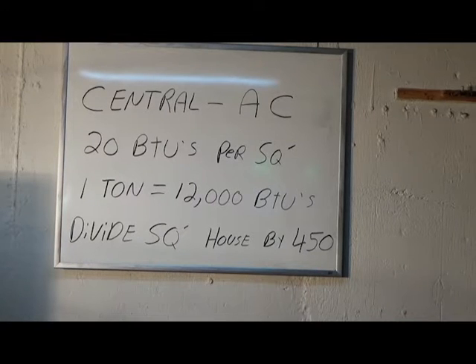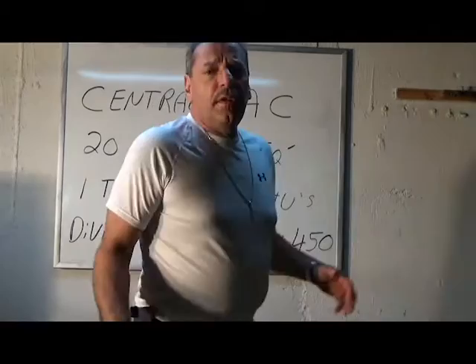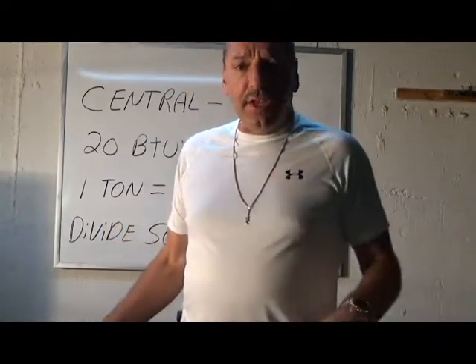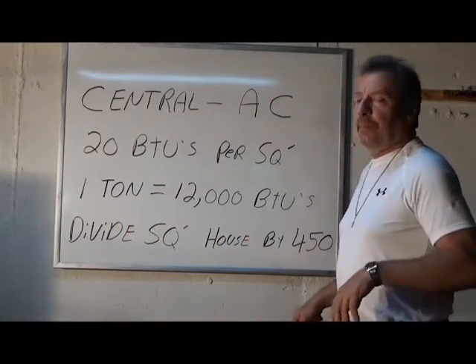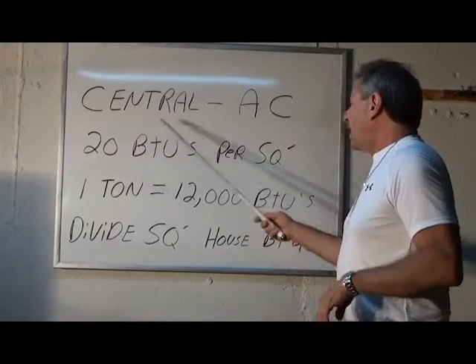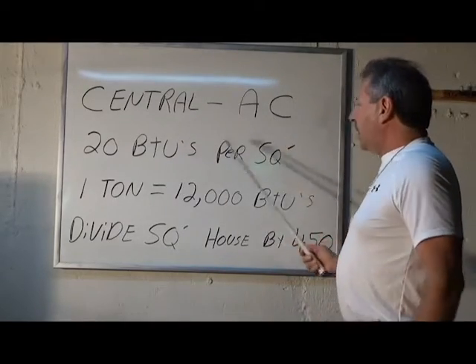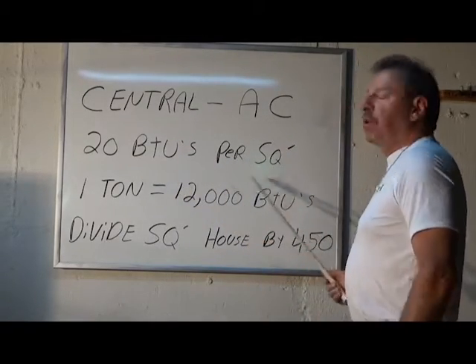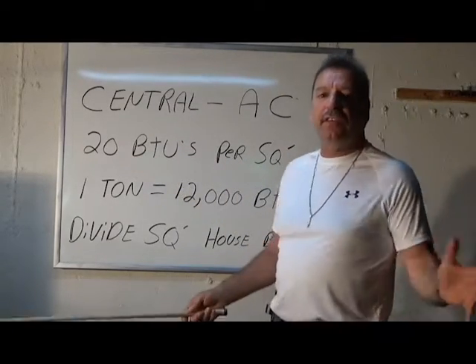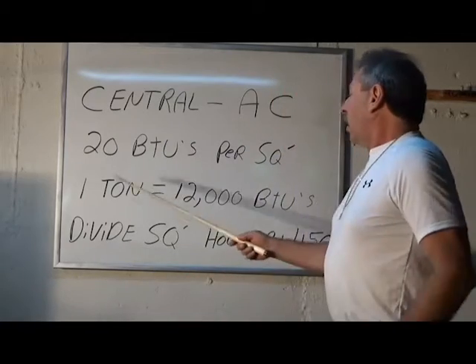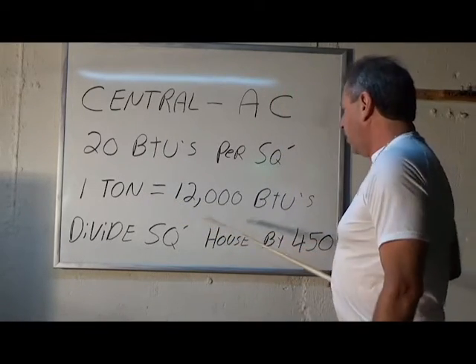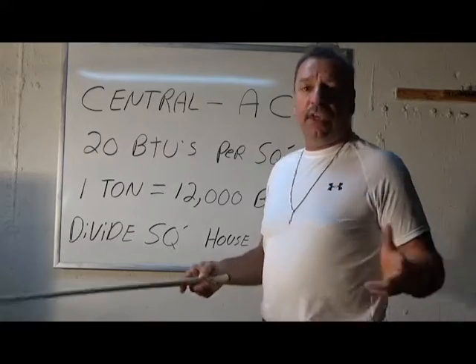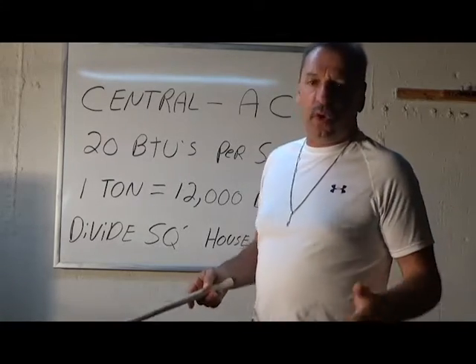Lou Depot here with just a quick rule of thumb on air conditioning BTUs — it's a little bit different than oil-fired, the boiler we just went over. For central air conditioning, you need 20 BTUs per square foot of living space in the house. One ton equals 12,000 BTUs, but it's very easy to figure out a house real quick.